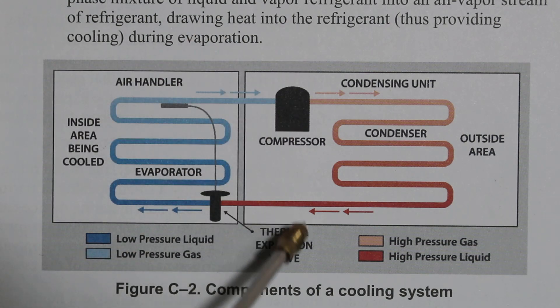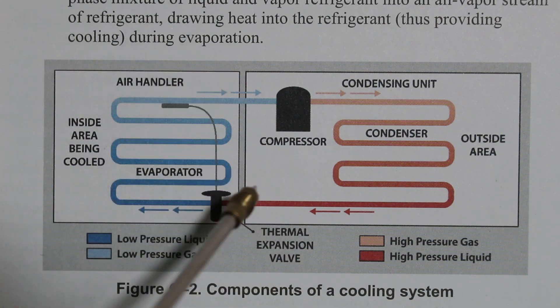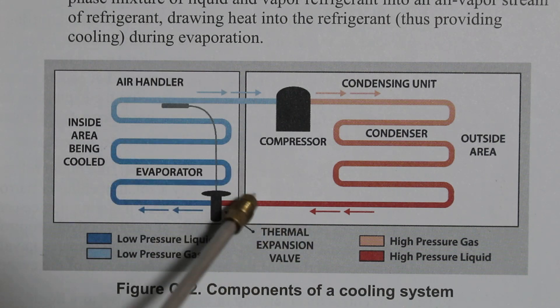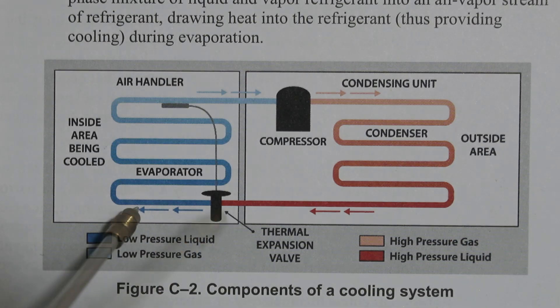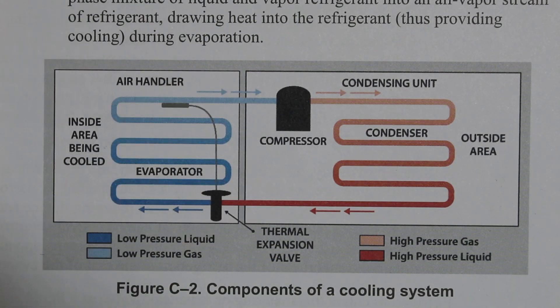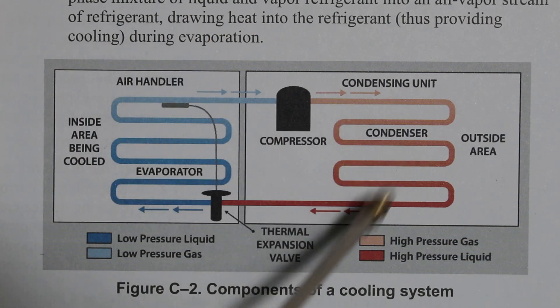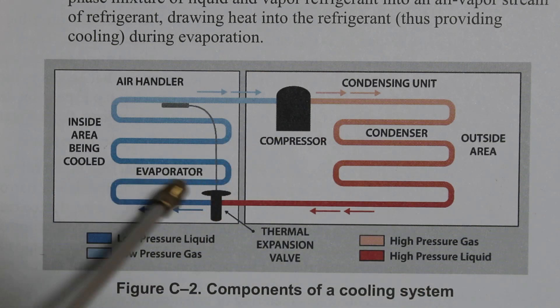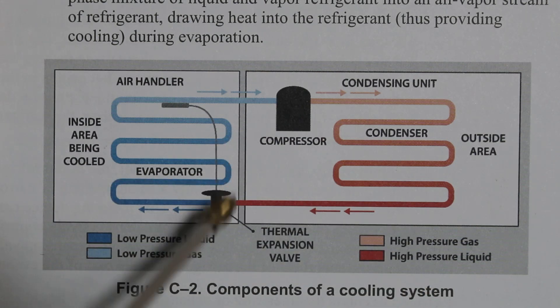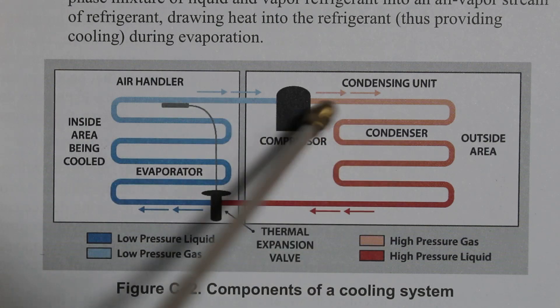In this diagram we have a thermal expansion valve as our metering device. Here we have a pressure drop: following our color code, we are entering as a high pressure liquid and leaving as a low pressure liquid. Our metering device is what separates the system from high to low — so on one side we are either a high pressure gas or liquid, and on the other we are either a low pressure liquid or gas. This is our low side and this is our high side.